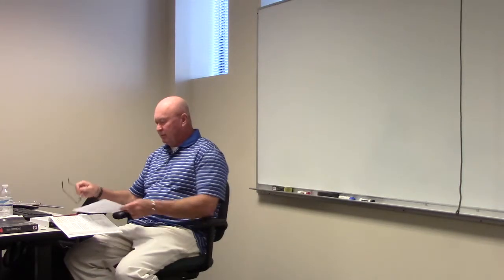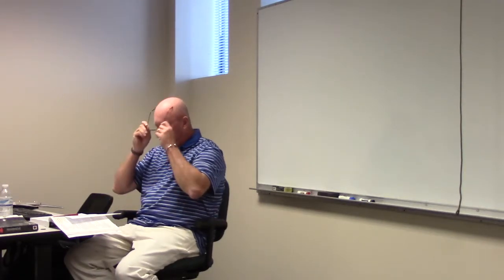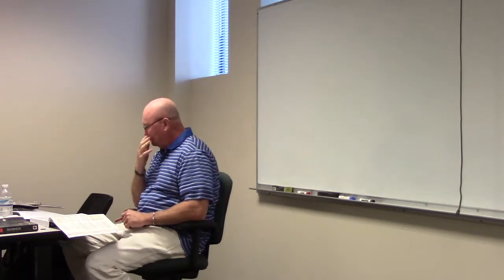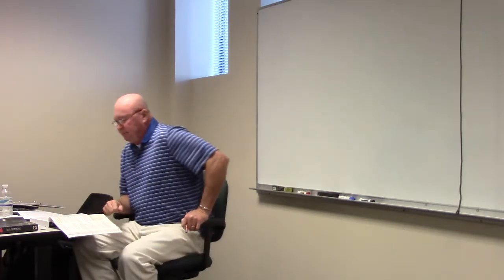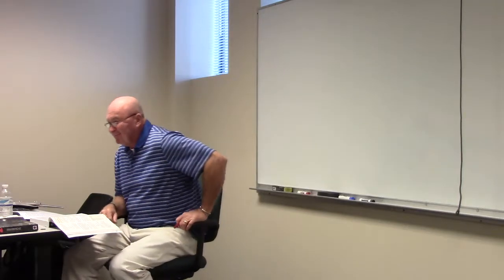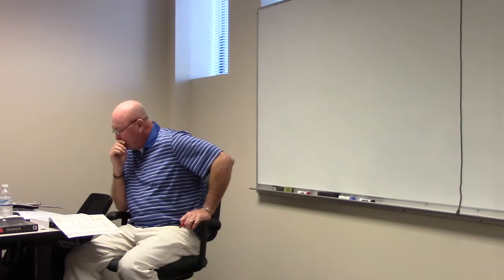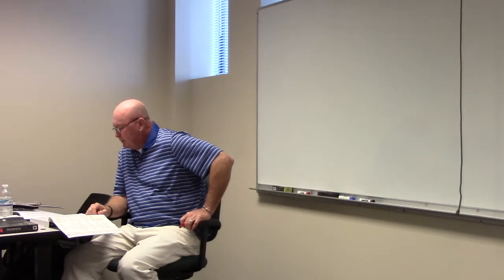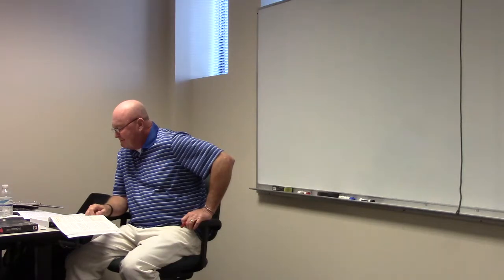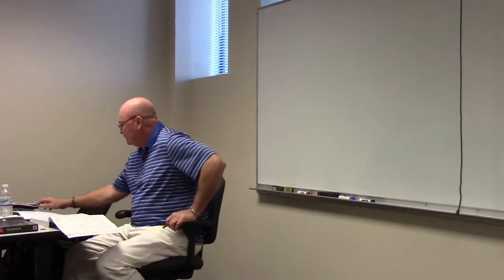I'm just going to ask y'all to read, kind of go back and forth and read one each. If you don't have the answer, that's fine. I'll help you find it. I have them. So, I did my homework. Okay, all right, so number one, Nate, start us off there. All loads that are continuous duty are multiplied by 125% to determine the overcurrent protection device and conductor size. You get that same thing, Cameron?